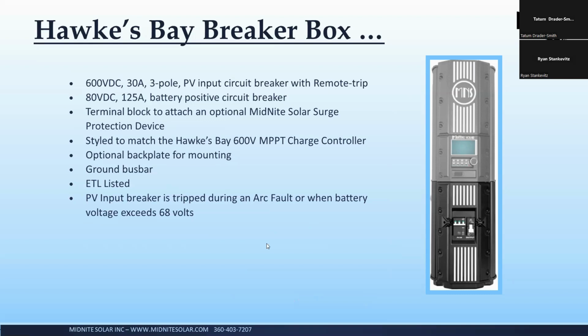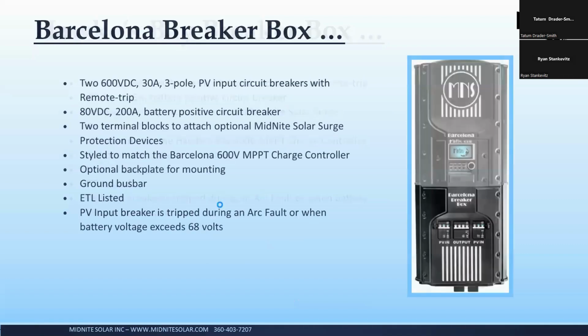It really didn't cost anything to add. We put it in there for the arc fault. The breaker was originally intended for the arc fault system. So if the arc fault detector detects an arc, it trips that breaker to make the system a little safer. So putting that analog circuit in there cost pennies, really, and it just added that extra level of safety that we hadn't really thought of until somebody brought it to our attention.